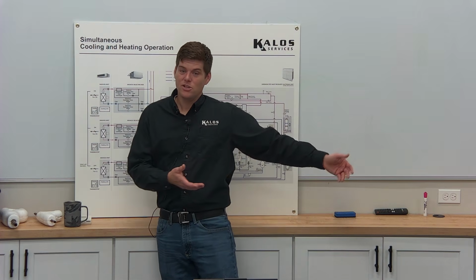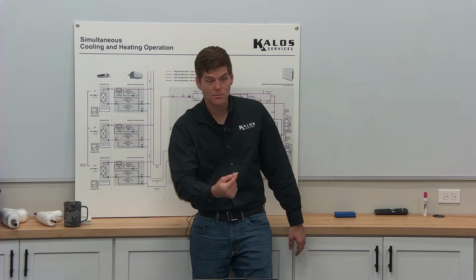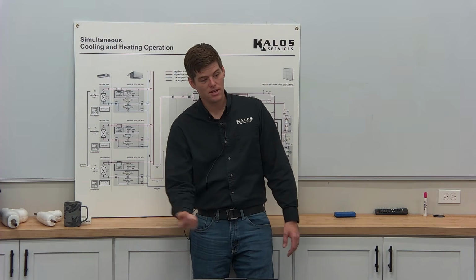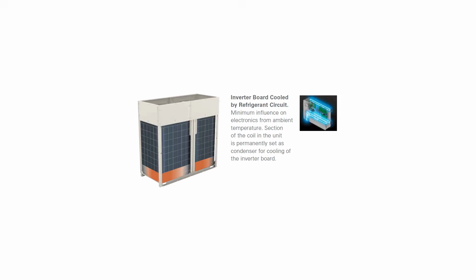Yeah. So all of these pieces of machinery, that bottom channel in the actual outdoor unit is constantly in a cooling mode state. That means there's hot gas going through the bottom channel, regardless of what mode it's in, generating liquid only for the inverter boards in the actual outdoor unit.